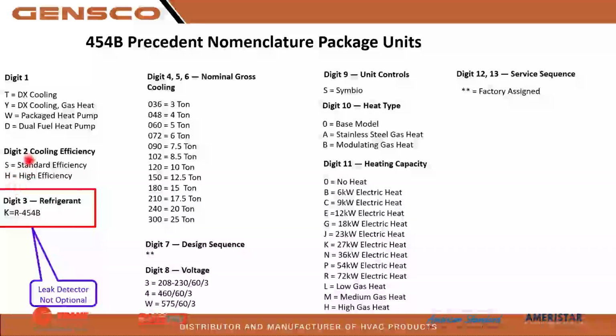S is standard efficiency, high efficiency. Digit 2, we usually see the YS or WS. This is what it was, J for 410A. Now we are going to see the K for 454B. So YSK or WSK, 454B, leak detector, not optional.